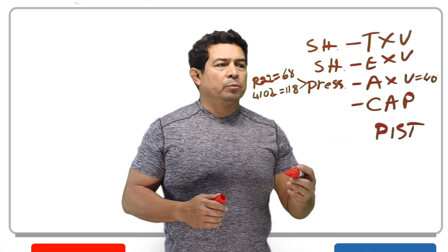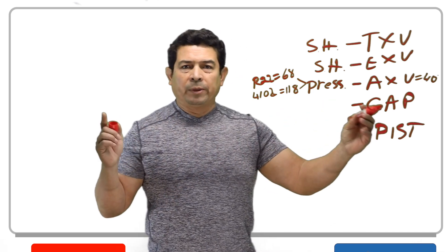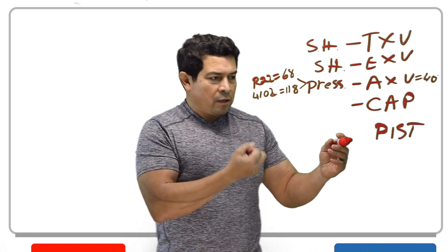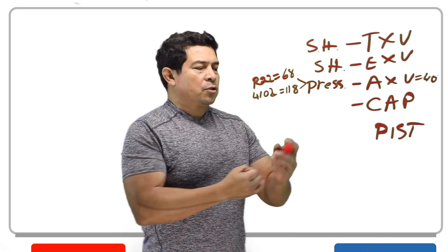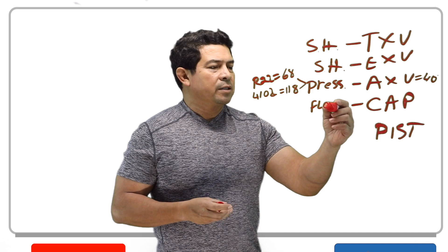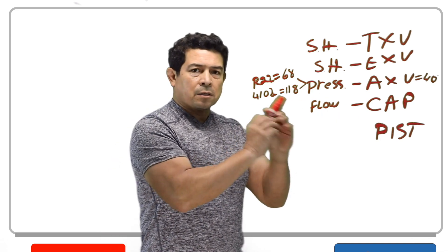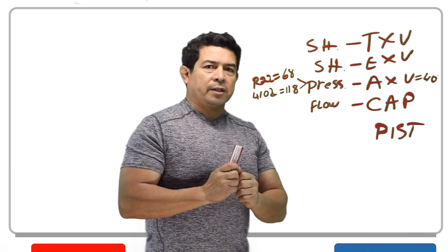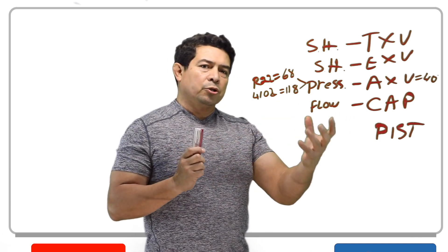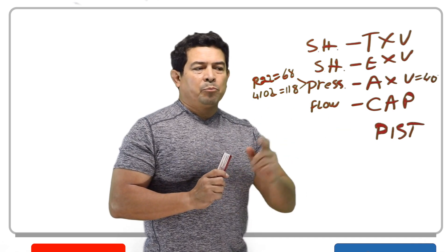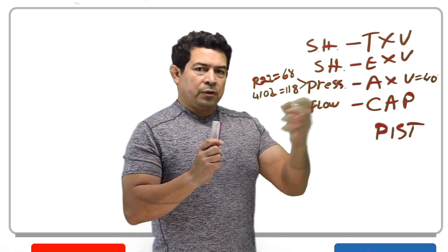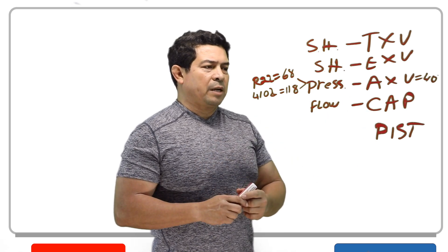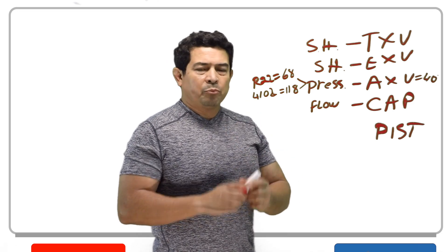The capillary tube is just a long piece of tubing. The longer it is, the more restriction it will have; the smaller the inside diameter, the greater the pressure drop. This one maintains constant flow into the evaporator, but it depends on the pressure on the high side and the low side. The higher the high-side pressure, the more flow into the evaporator; as the evaporator pressure increases, it restricts the incoming flow. They don't use it that much anymore, but there are some out there.